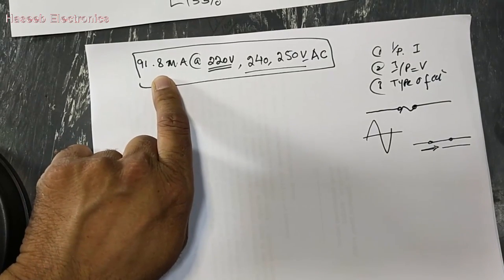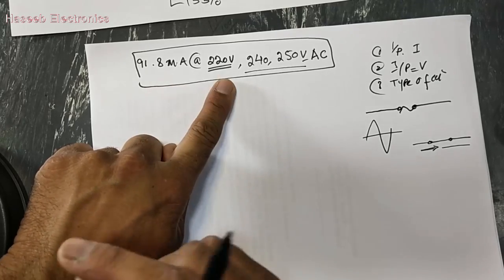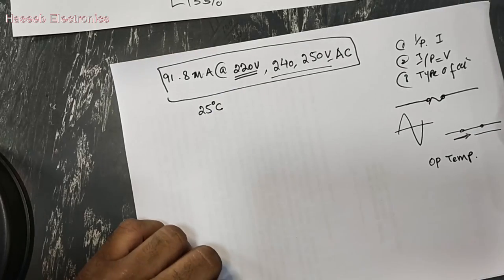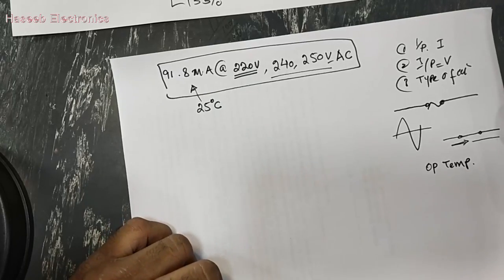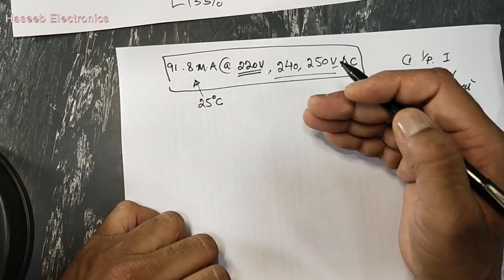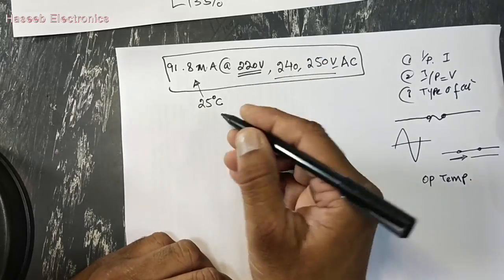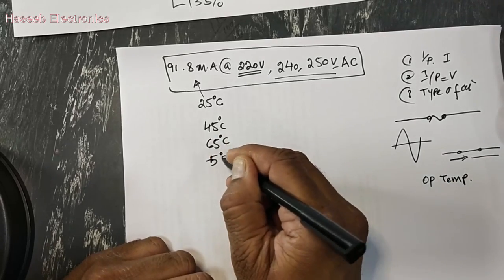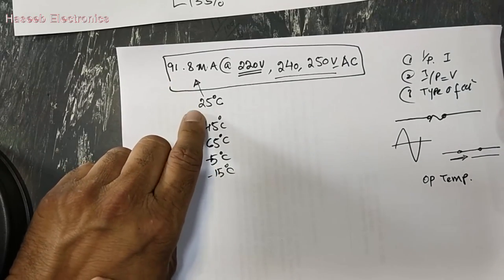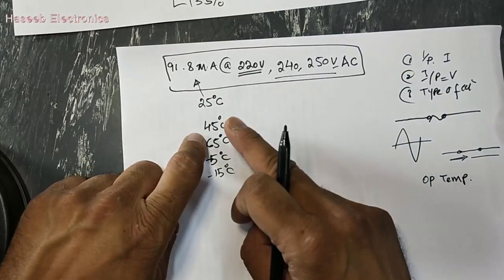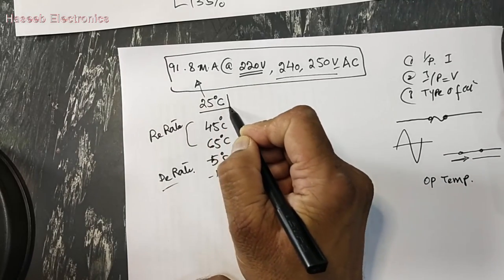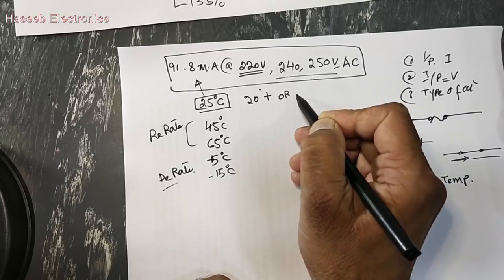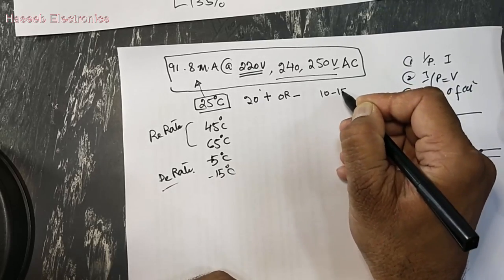The fourth parameter: any fuse value is rated at 25 degrees centigrade operating temperature. If we are using it at 25 degrees that value is fine, but in real conditions a power supply operates in different weather — maybe 45 degrees, 65 degrees, or even minus 15 degrees. With each 20 degree change in ambient temperature, we have to re-rate or de-rate by 10 to 15 percent of the current value.